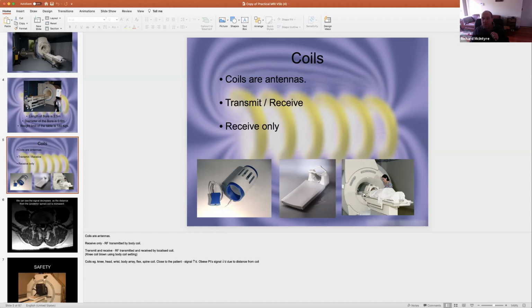We've got different head coils. We want those coils to be as close to the body part as we can. If we're doing a head scan, we want coils very close to the head. If we're doing a spine scan, we want coils very close to the spine. We don't care about anything else; we only care about what we're imaging. If we're doing a wrist scan, we want coils very close to the wrist. We don't want to use a head coil for a wrist scan, because that head coil is too far away. Once the hydrogen protons in the wrist relax back and give off their signal, you lose too much signal between that wrist and the head coil.